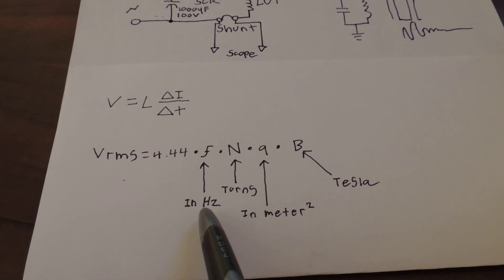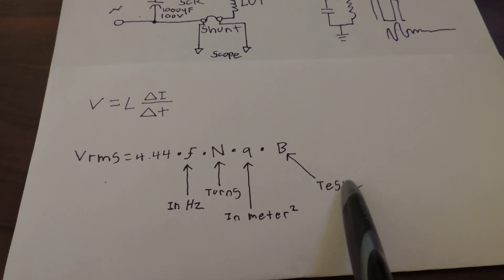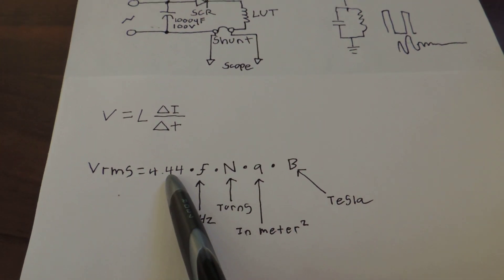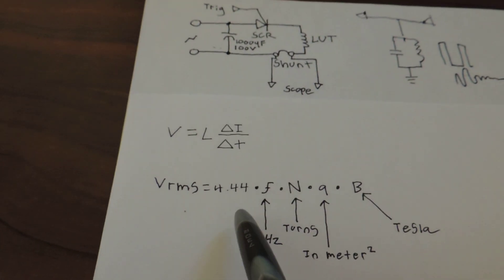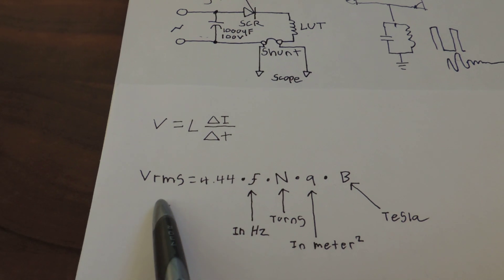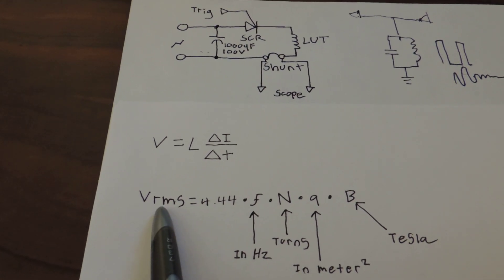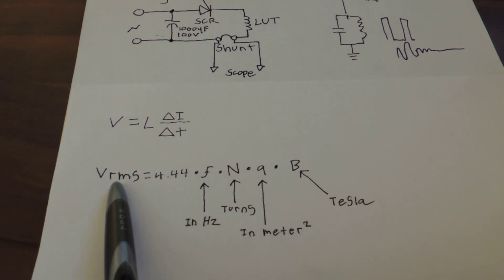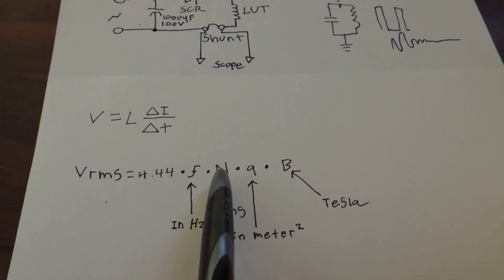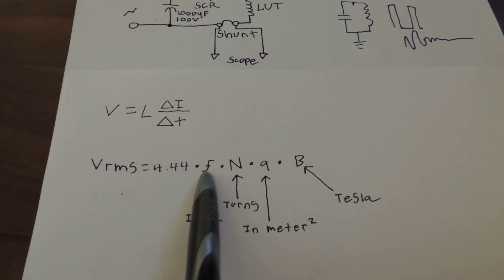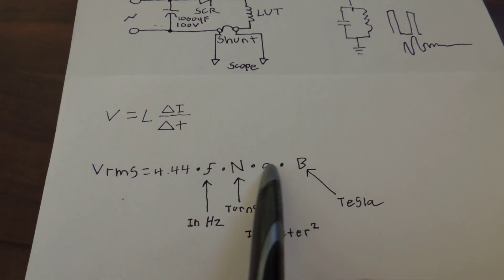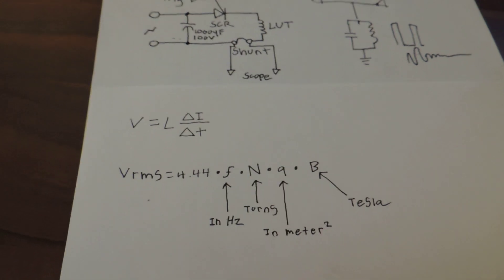When you take all these values and you multiply them together, and multiply them times the constant 4.44, which is the square root of, I can't remember off the top of my head, you get a voltage RMS. This voltage RMS is the maximum amount of voltage you can apply to the fewest number of turns at a given frequency that will not saturate this core for this cross-sectional area and this peak flux density.